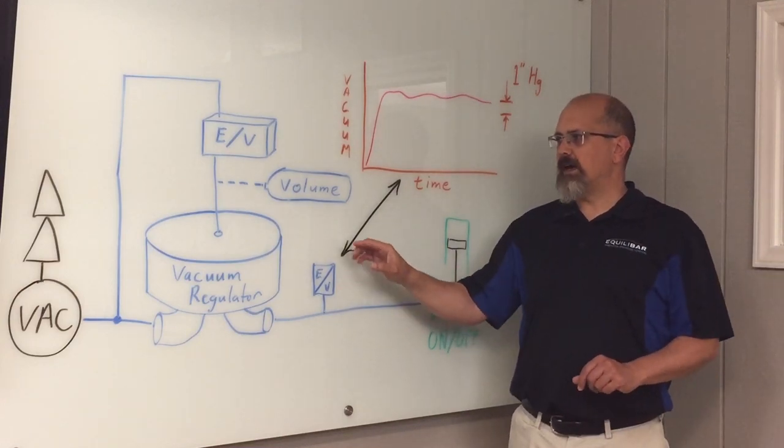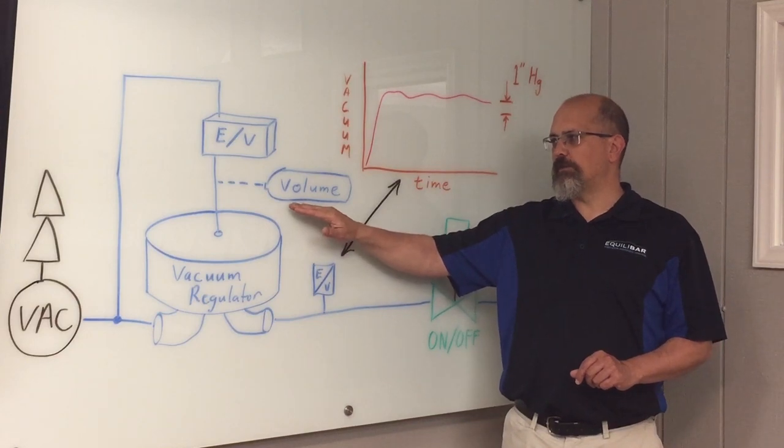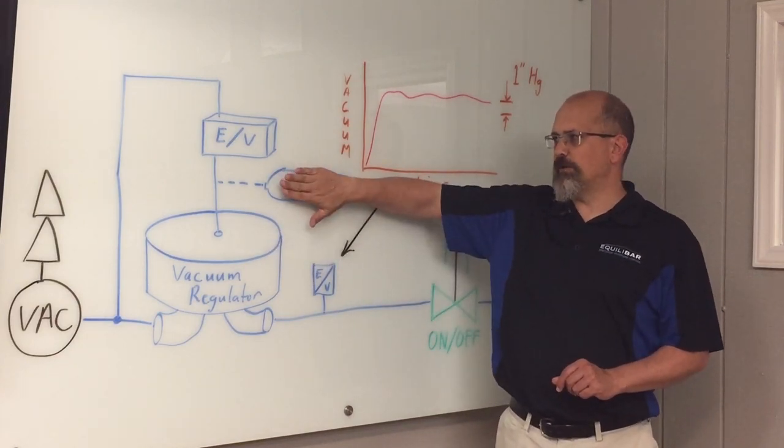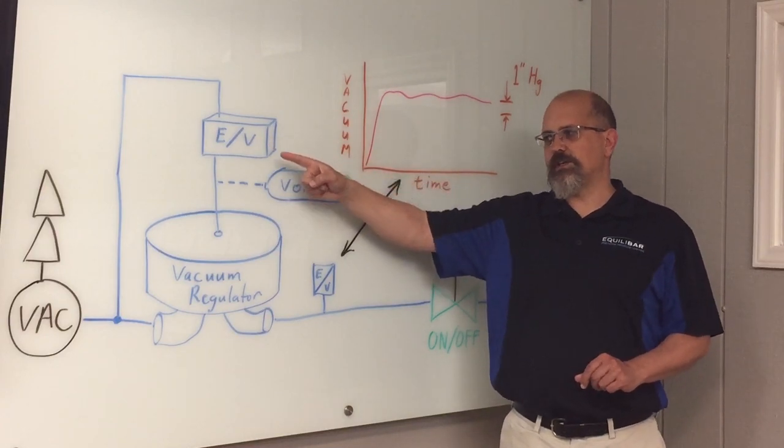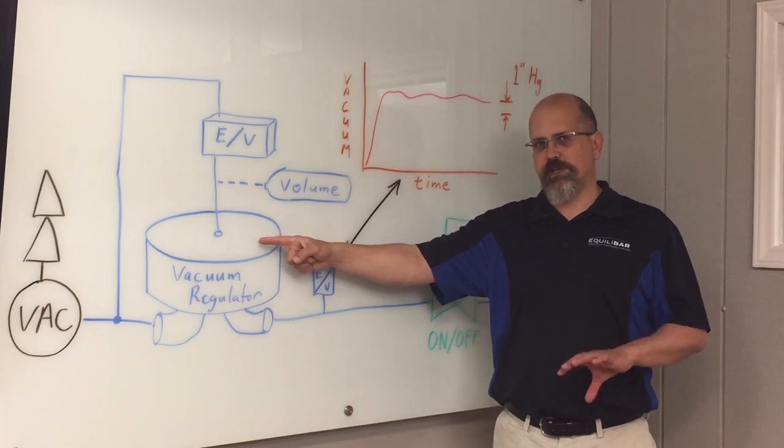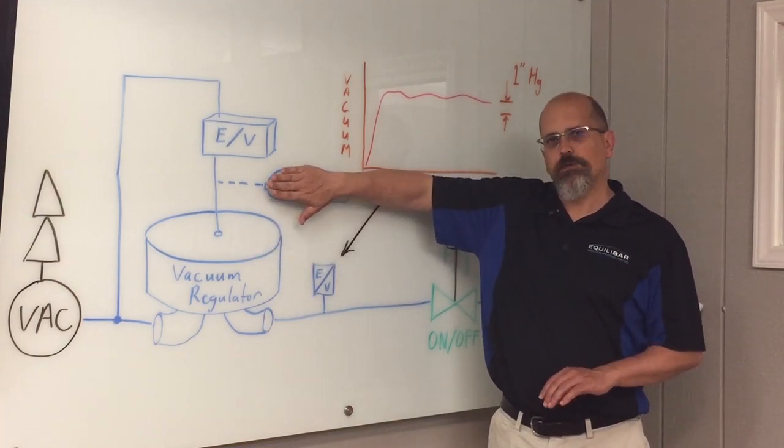One thing we're going to do in the lab is we're going to toggle a volume in and out of the pilot. So with no volume, the electronic regulator is able to change the pilot signal very quickly. So if you need to change the vacuum setpoint quickly, we'd go with no volume.